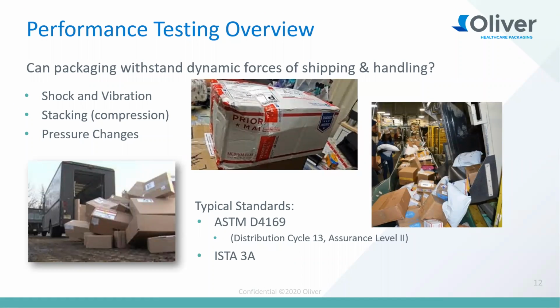So it's one of the more rigorous, and it is challenging the packaging more than the other distribution cycles. So it really matches what these are being shipped at. And the assurance level 2 that we have listed there is very important. And there's 3 assurance levels. The assurance level 2 is the most common, and the standard actually directs you to use that unless otherwise stated in your risk assessment. So assurance level 1 will actually provide a higher level of intensity to your package, while assurance level 2 is a lower level of intensity.